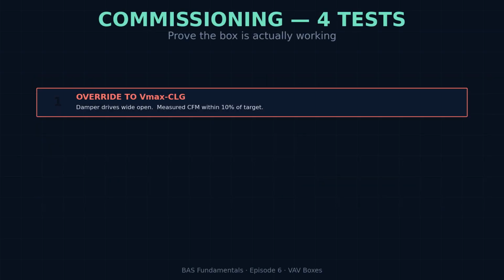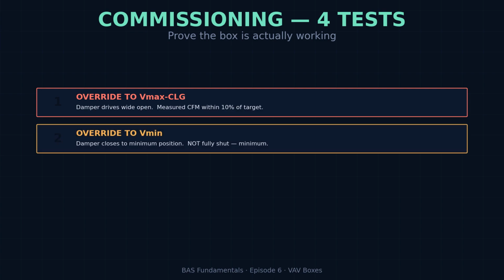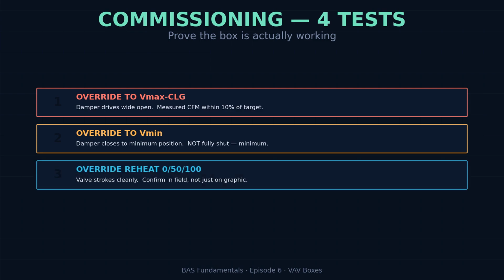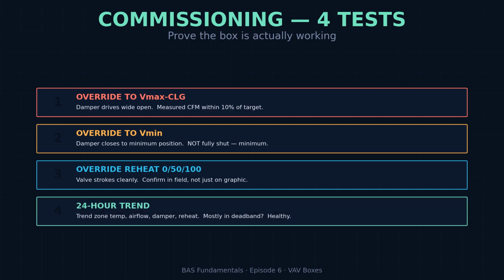How do you commission a VAV box? 4 quick tests. 1. Override airflow to Vmax cooling and check the damper drives wide open and the measured CFM is within 10% of target. 2. Override to Vmin and confirm the damper closes to its minimum position, not fully shut, minimum. 3. Override reheat to 0, 50, 100 and watch the valve stroke. 4. Trend zone temp, airflow, damper position, and reheat valve for a full day. If you see the box happily in deadband most of the occupied hours, you've got a healthy zone. If it's hunting or stuck at one end, you've got work to do.